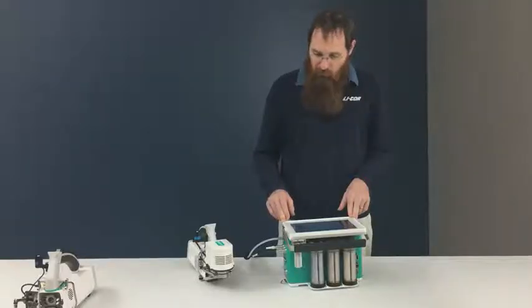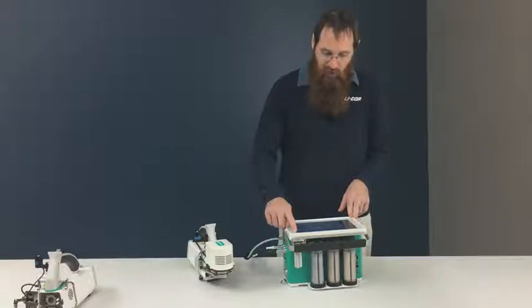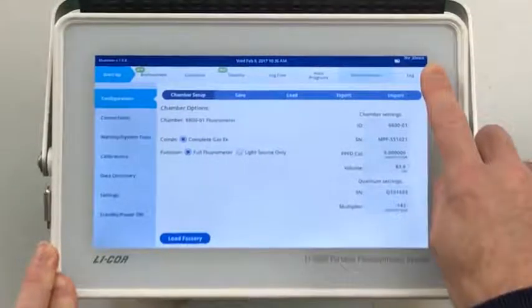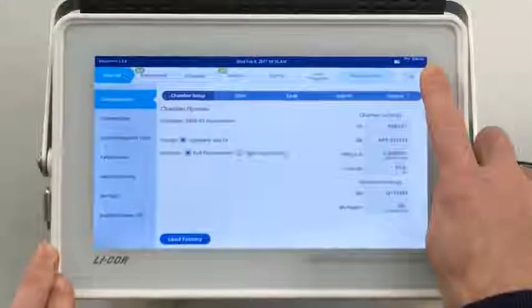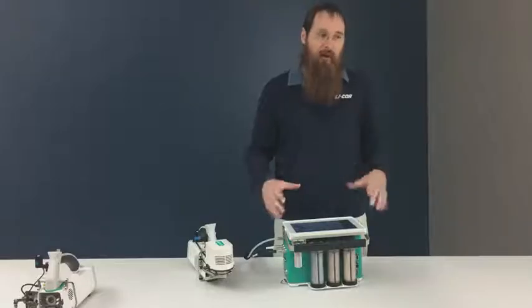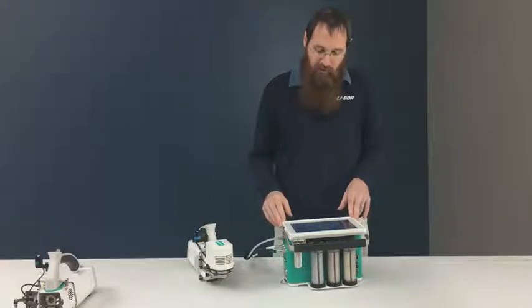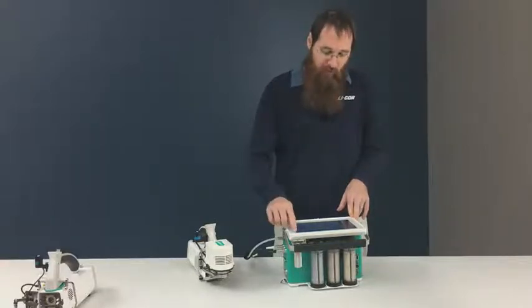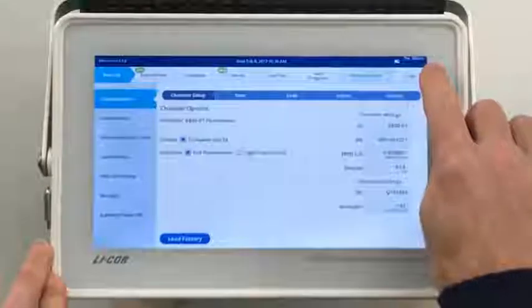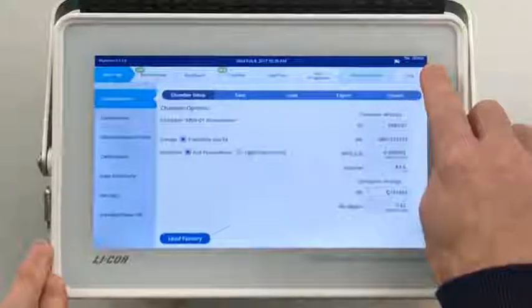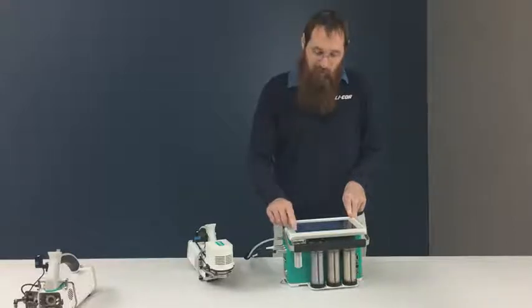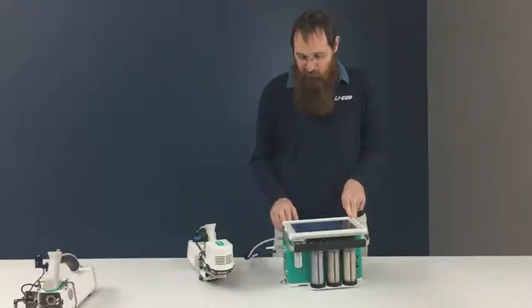I guess I didn't talk about this with the hardware - now is as good a time as any. You'll note there's a countdown here at the top. This instrument uses modern battery technology with high charge density, so we get a lot of runtime, and we tell you how much runtime is left on those batteries. Right now my instrument is running independently on battery power, so this shows how much charge is left - 7.5 hours.